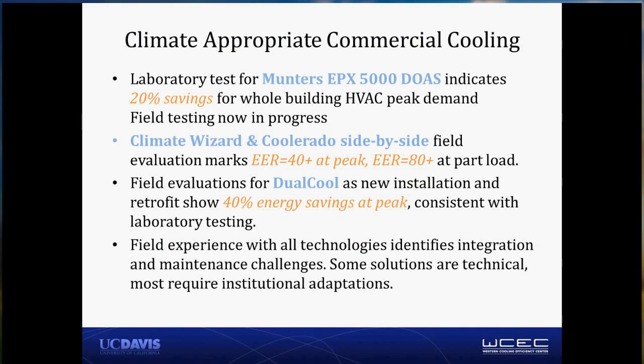So today, I'm going to dive into some details about 3 different pieces of equipment that we've had some recent success with. Number 1, I'll touch on our laboratory tests for the Munters EPX 5000, which is a dedicated outdoor air system. All of our numbers indicate that the application of this one unit on an existing, say, big box retail facility could drive 20% savings for HVAC demand during peak operating conditions. And we're right now running a field evaluation, which is in progress with PG&E and a large grocery chain located in the Bay Area.